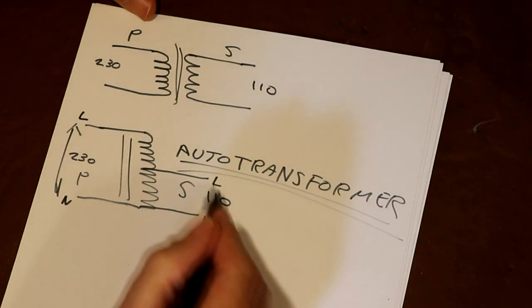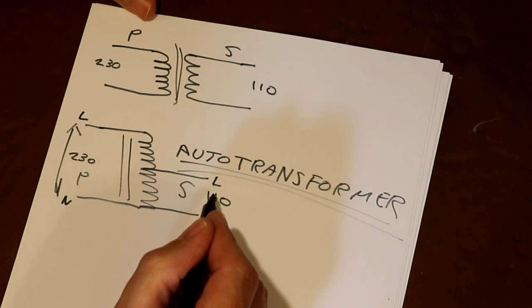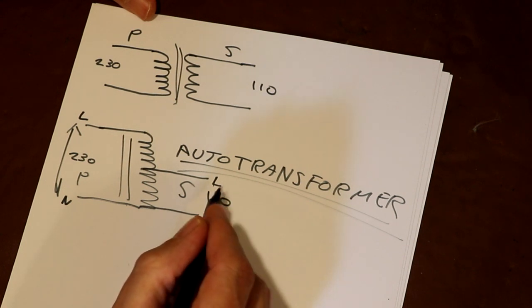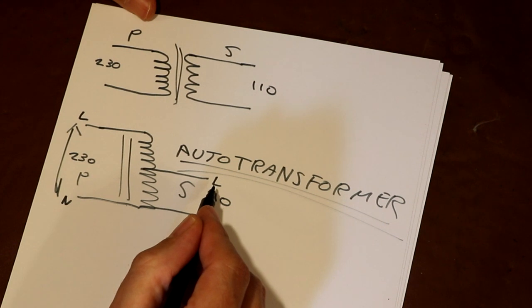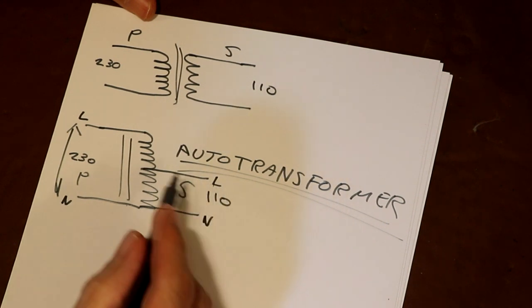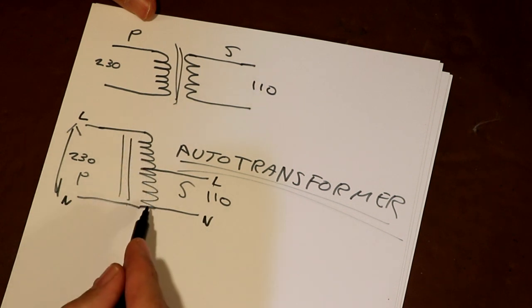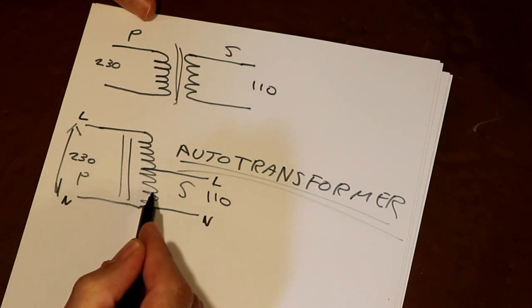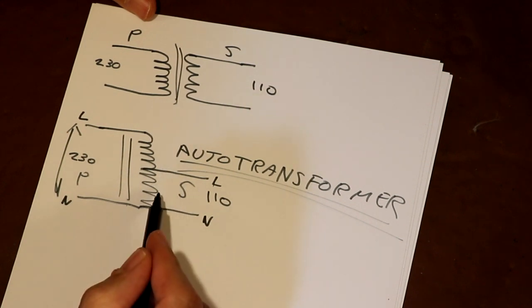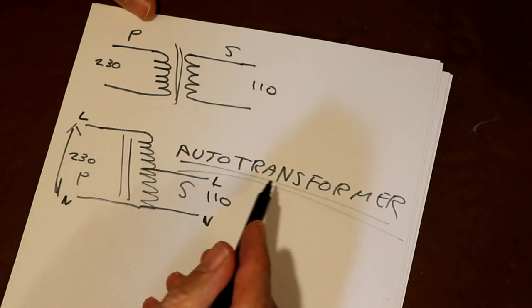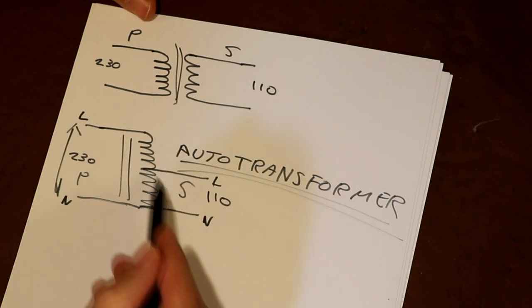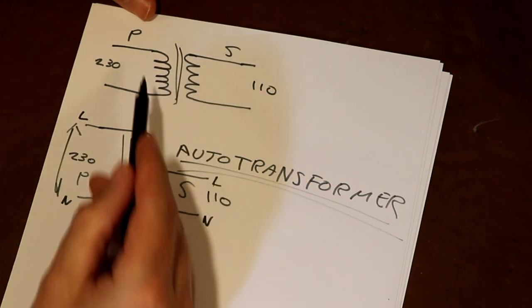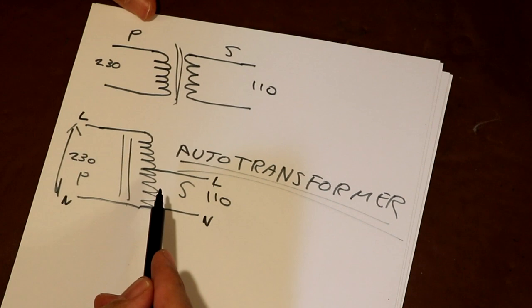But having mentioned these disadvantages, one of the main advantages of the auto transformer, if you don't need isolation, is that it's much cheaper, because we've only got one copper winding here, so there's much less copper in it, and typically there'll be about 50% less copper. Copper's very expensive, so an auto transformer will probably cost about 50% of the price of a standard transformer, and that's a big advantage, isn't it?